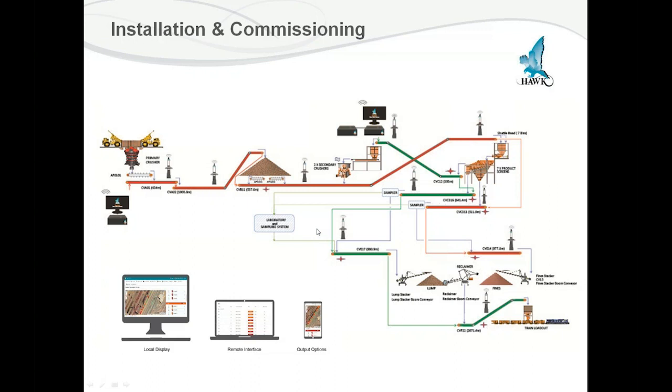The idea is that we cover these fibers. You can see the linkages in red and green, depending on where these route to. And you're actually able to cover a remarkable amount of belts with one or two of these devices. These run a fiber down each side of each conveyor, so that way we give a failure indication not only to say that a particular frame is having a problem. We also can indicate left, right, center based on the difference between the two channels on that conveyor.